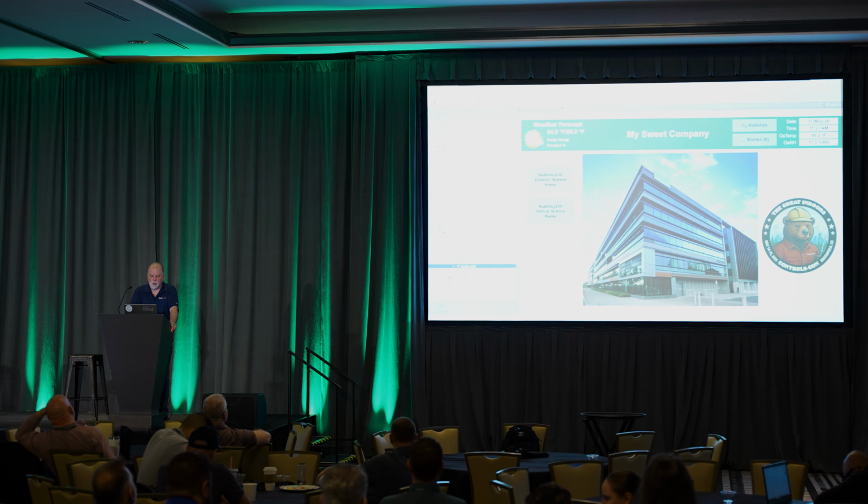Now, as far as templates go, and for those of you that might not know what templates are, perhaps what a template is a reusable piece of code, right? It includes the component, which in this case is a LAN device, and it has all the points already mapped in it, and it has history extensions, alarm extensions already set up in it, already has graphics included. And we have version control associated with this, right? So there's a version number that's there, and when we make changes, then we can add more comments to it. We can keep old versions of our template.